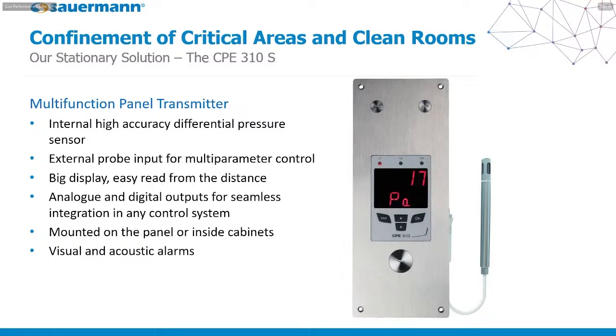So we have a couple of special models specifically geared for that. And it's very nice that it's flush mounted into the wall. It looks very clean and very professional in terms of fitting into the overall look of the building or the particular room. And as you can see here, sometimes you can have external probes for this, if you want to measure from very exact locations, like, for example, right at the door coming in or out of the room. We have analog and digital outputs coming from this. And as I mentioned before, we have both visual and acoustic alarms that can be tied into the transmitter to let you know if the pressure outside the room is getting almost the same as what's in the room, or possibly even greater, which would be a problem. In that case, you would have to have the maintenance people come in and work on the system to ensure that you have the greater pressure within the clean room.